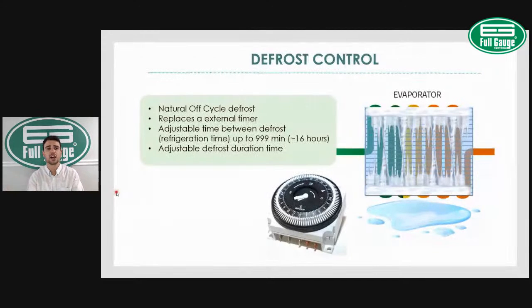And here are some of the characteristics of our off-cycle defrost option. You can adjust from 0 to 999 minutes. That means about a 16-hour interval. So again, you can adjust from 4, 6, 8 hours all the way up to 16 hours. And you can also disable this defrost function, since some applications might not require defrost. And in the next slide, we're going to see what the defrost parameters are.